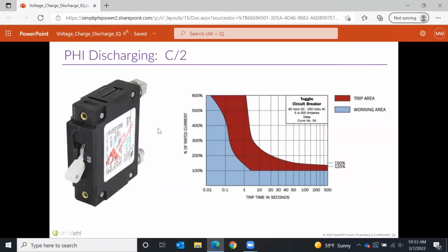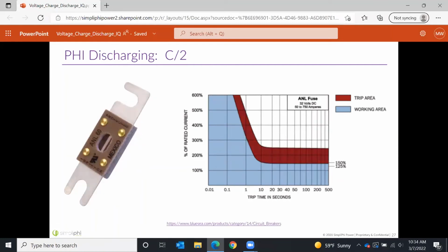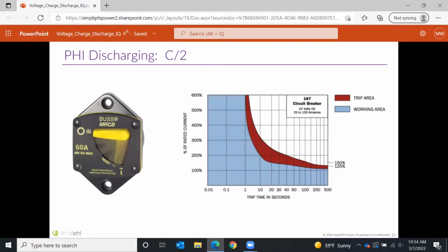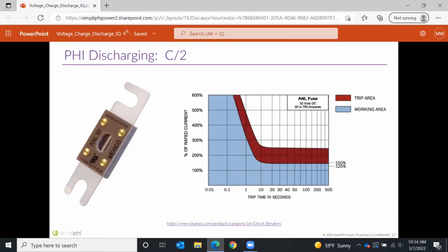Now we move on to this different type of breaker, and we see that it's going to trip at exactly 100% of its rated capacity. So you've got a 60 amp DC breaker, it's going to trip right at 60 amps. And then this fuse, it's not going to trip until almost 150% of its rated current. 150% of 60 amps is 90 amps, so that's not really enough protection for these batteries if you're not sized properly. So this is why using overcurrent protection to protect your batteries is not a great idea. Realistically, any of these would probably be fine for protecting a certain size wire, but in terms of protecting batteries, you really want to size the system properly in terms of battery to inverter ratio.